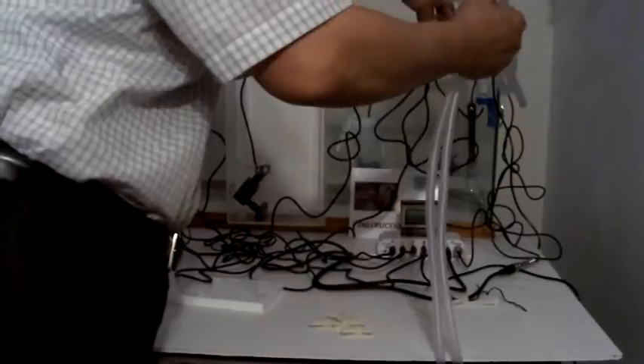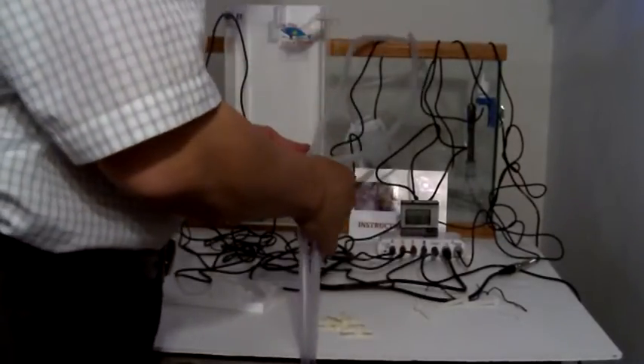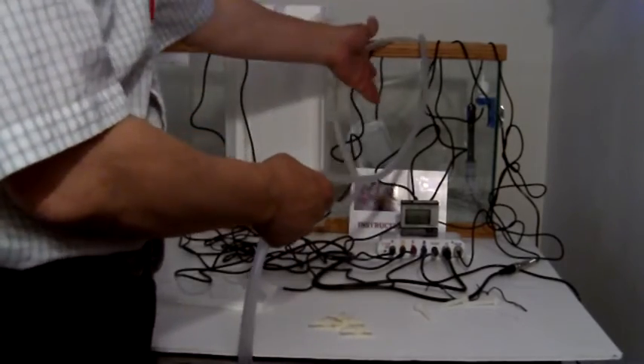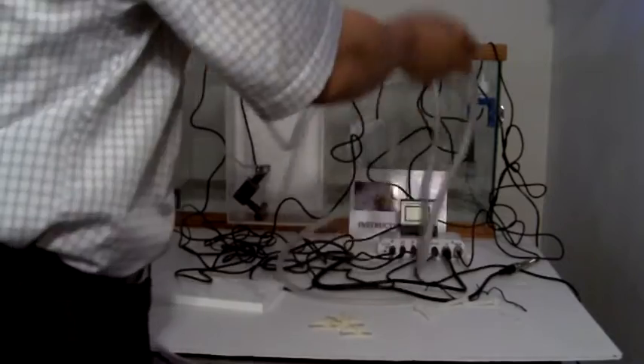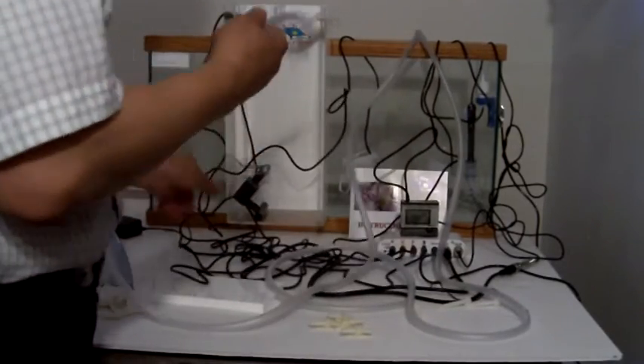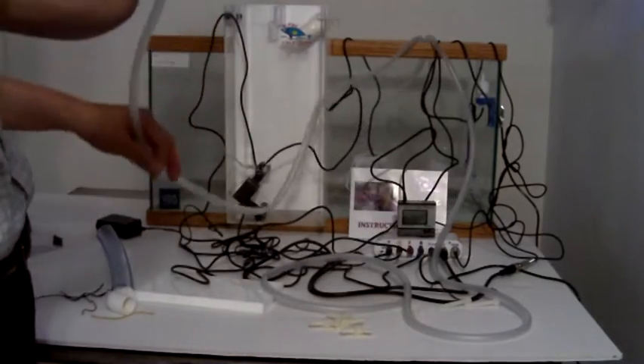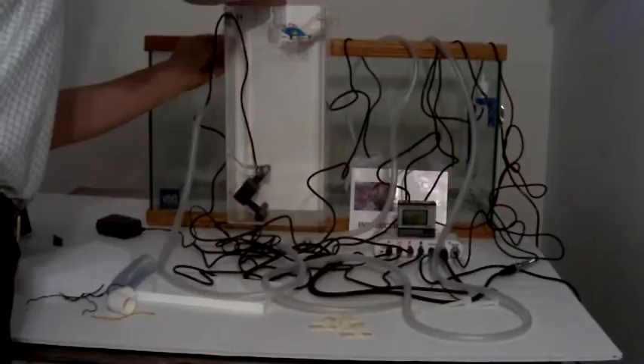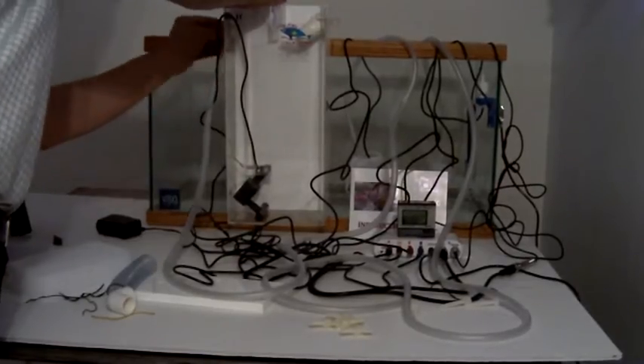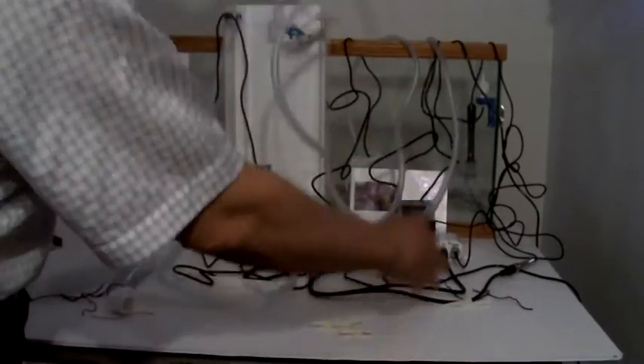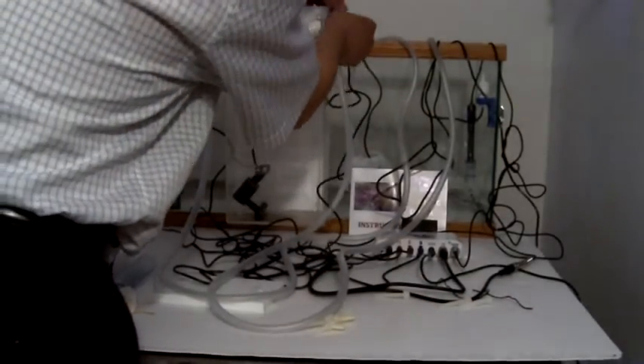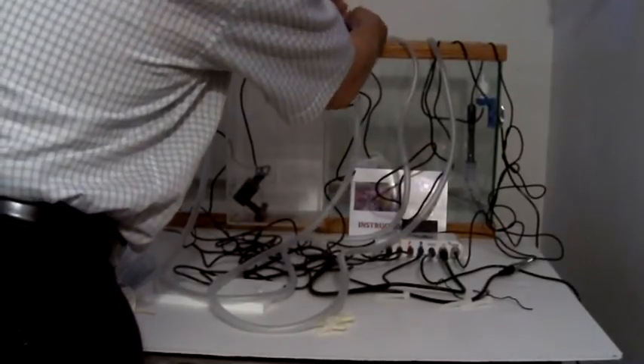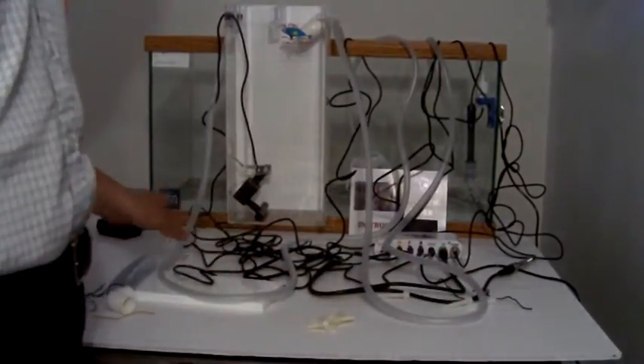After that, you just put these two pumps into the freshwater reservoir. Since I don't have a two-reservoir setup, I'll just put it into one of my demo tanks here. For the bypass pump, this is the feed pump — you connect it to the input side of the reaction chamber. For the other one, the bypass pump, you put it through the side hole and into the tank. So now you have set up all the connections.